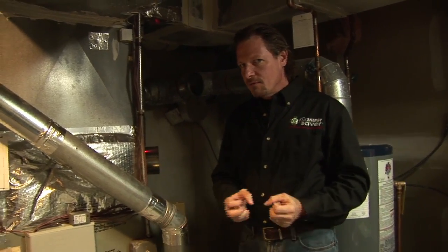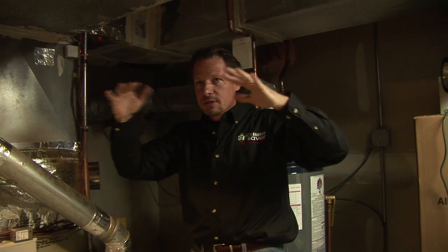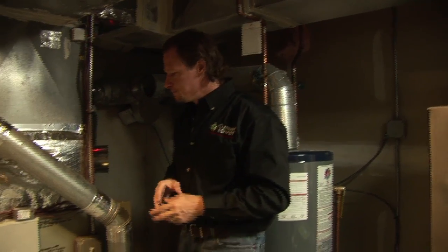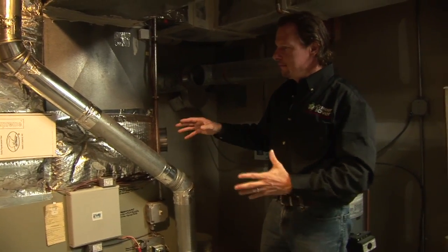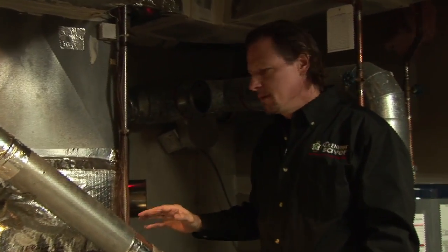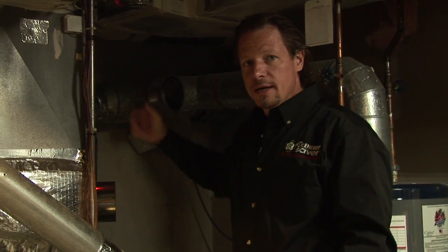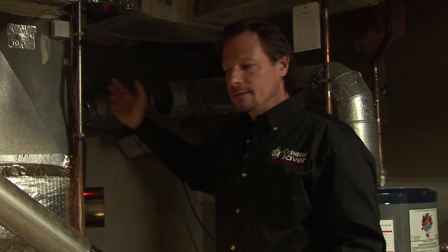In other words, if we're drawing air from inside the house to put up the chimney, well, we're depressurizing the basement as a result. And the new air, to replace that air, comes from outside. Because we created a vacuum in the basement, we're sucking air in through the rim joists, through the basement windows, through the cracks and gaps in the top of the foundation and the building assembly. And so that air has to be heated, cooled, dehumidified to be made comfortable. So a high efficiency equipment would have a dedicated air supply right to the combustion chamber and a sealed pipe to the exhaust, so it doesn't draw any air from the conditioned space and cause this depressurization, which sucks unconditioned air from the outside into the building.